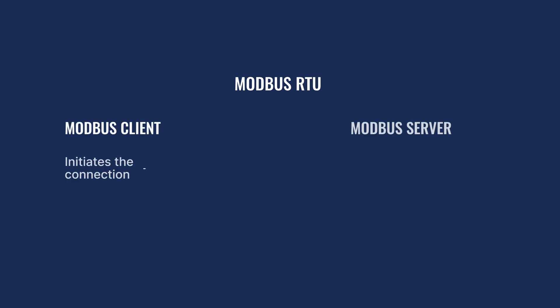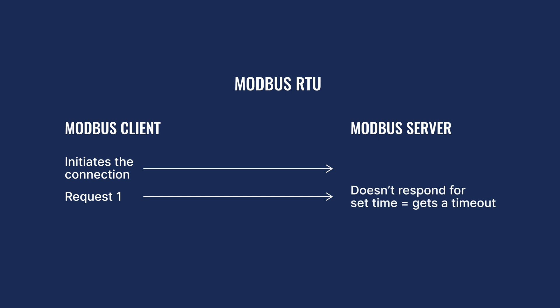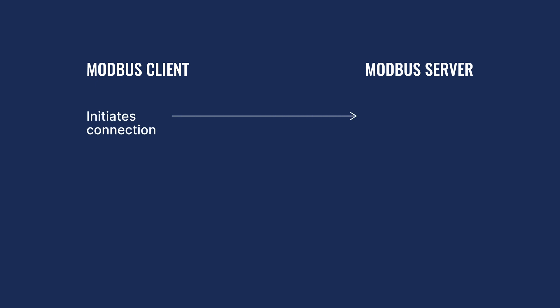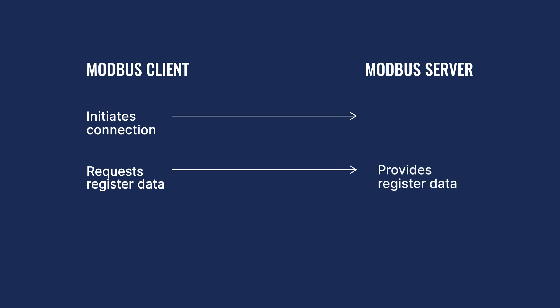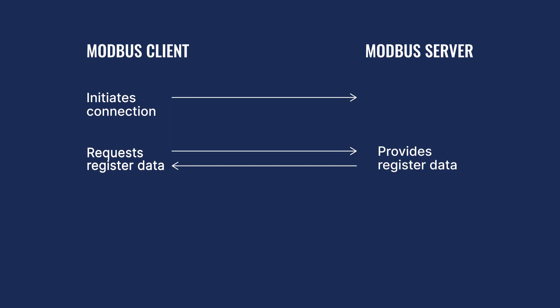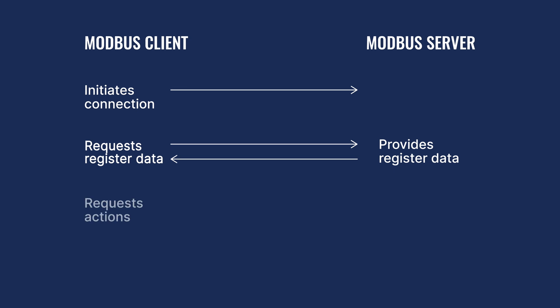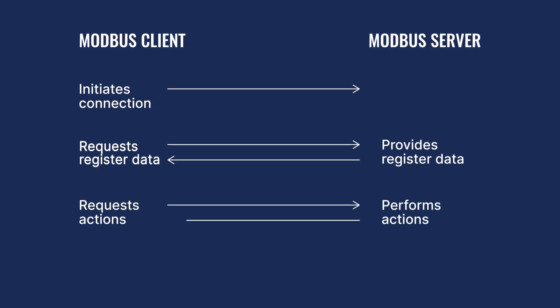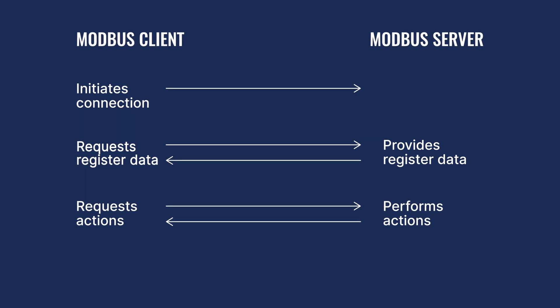With Modbus RTU, the client also initiates communication but relies solely on the set timeout value to determine whether the Modbus server is ready to perform actions or other requests. Essentially, the Modbus client initiates the communication by establishing a connection and then requesting particular information or actions from the server. The Modbus server acts as both a listener and a responder, waiting for the client to connect and issue commands so that the server can perform the requested tasks.